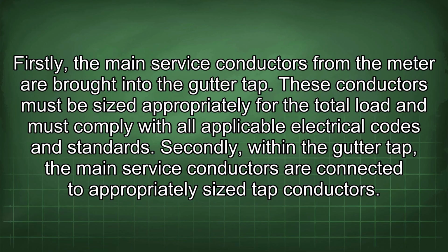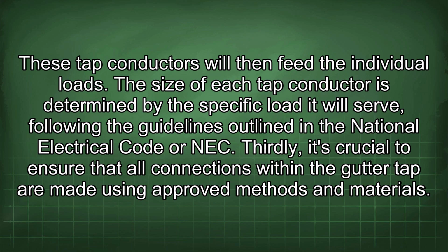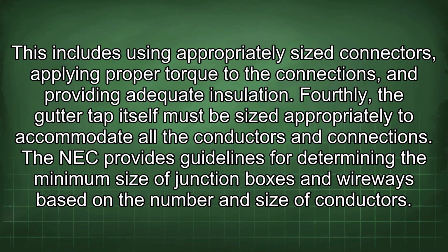Secondly, within the gutter tap, the main service conductors are connected to appropriately sized tap conductors. These tap conductors will then feed the individual loads. The size of each tap conductor is determined by the specific load it will serve, following the guidelines outlined in the National Electrical Code, or NEC. Thirdly, it's crucial to ensure that all connections within the gutter tap are made using approved methods and materials. This includes using appropriately sized connectors, applying proper torque to the connections, and providing adequate insulation.